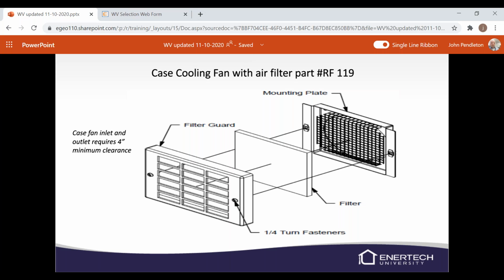It'll probably need to be replaced about once a year. It's going to really depend on where it's sitting, how dusty the area is. But again, case inlet fan's got 2 little quarter turn fasteners on it. You pop those, pull it off, and your filter material's right underneath there. Don't operate it without a filter in there, because then you're going to get all that dust and debris on your controls, and that could definitely short things out. So we do require a 4-inch clearance on the sides of the unit so that we can pass air through that cabinet.